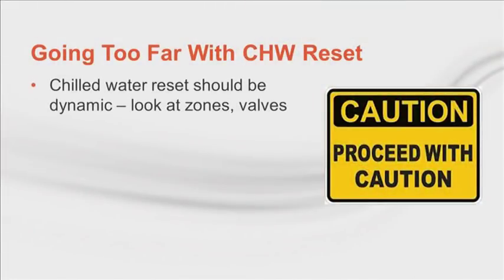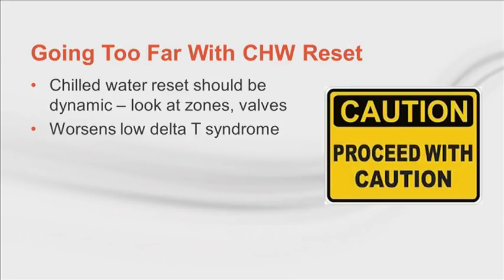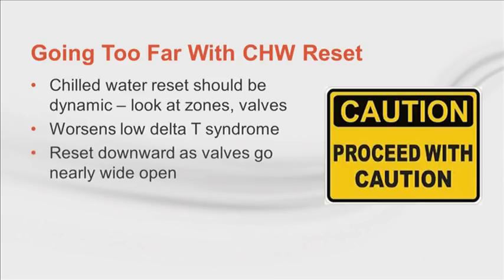Now, the caveats. Chilled water reset, when used, should be dynamic and not a permanent override. With this strategy, too much of a good thing can drive your system off a cliff. That's because if low DeltaT syndrome is present, that is, the DeltaT is smaller than it should be given the load condition, chilled water reset can make the problem worse. Zone temperatures and/or valve position should be monitored, and the reset should be released when loads get too high for the warmer temperature water to effectively cool. Release or reset downward as valves and/or fan speed get to nearly wide open in one or more zones.